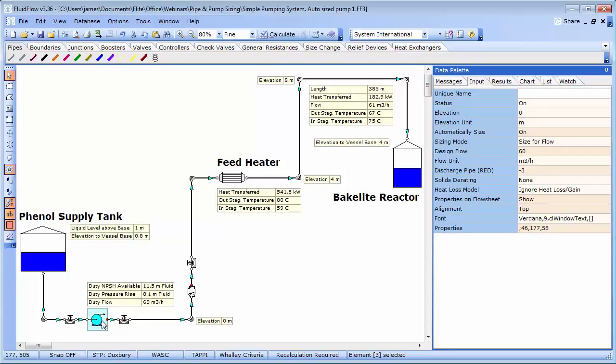At this point in the process you may ask yourself where do I start? To size any pump or compressor, transport any fluid, the first two steps we should consider are define the flow rate that the pump is required to deliver and this is usually determined from the design mass balance of the process in which the pump is installed.